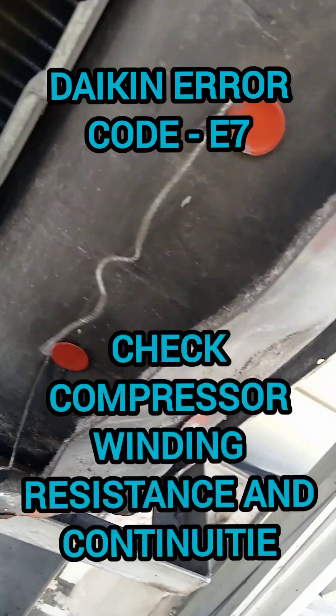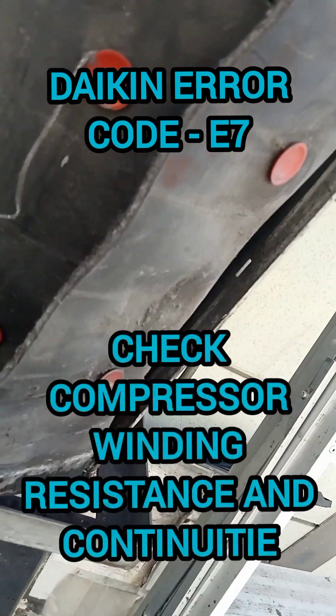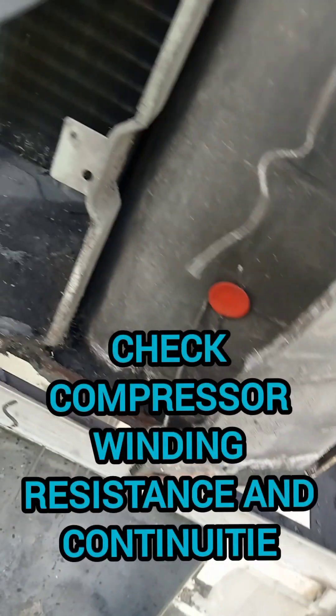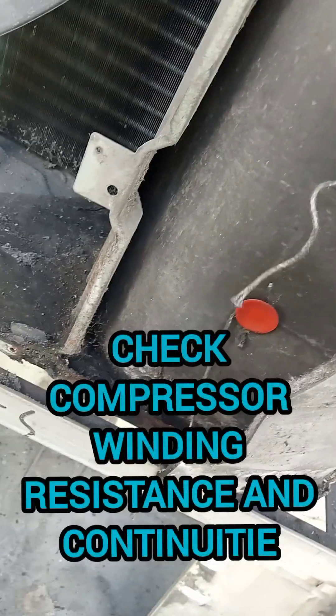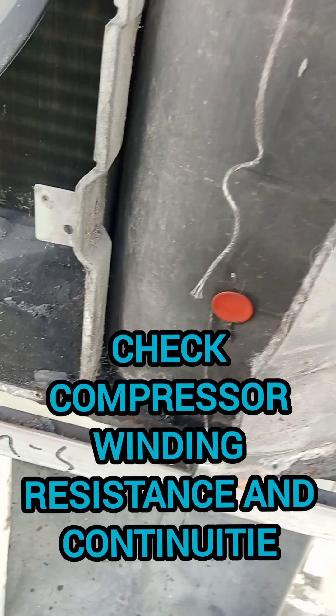In this video we need to check the compressor winding resistance and continuity to determine if the compressor is okay or not. The error code is E7, and we already checked the PCB board — the fan motor is the problem.